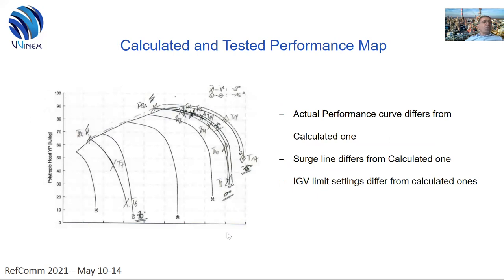To demonstrate this point, here is the performance map of the real tested blower. You can see how much the tested performance curve differs from the calculated one. The performance data recorded at 70 degrees of inlet guide vane position is more close to the 60 degrees that was calculated. The measured surge line is quite different from the calculated one, and the IGV limit settings are also different from the calculated one. All these factors create difficulties during the testing of the panel together with the compressor on site, or for fine-tuning of the controller routine.